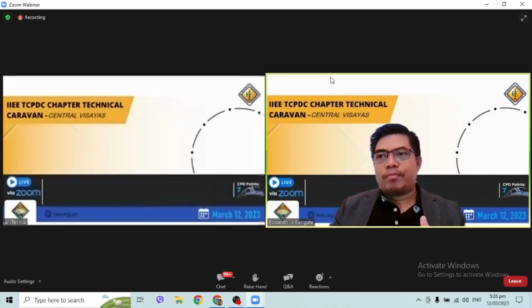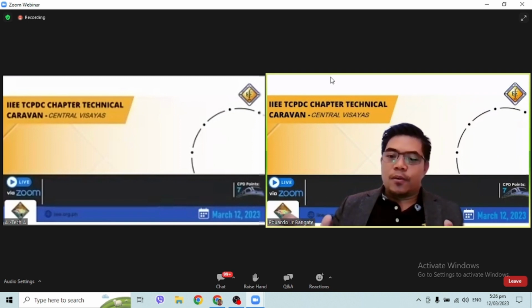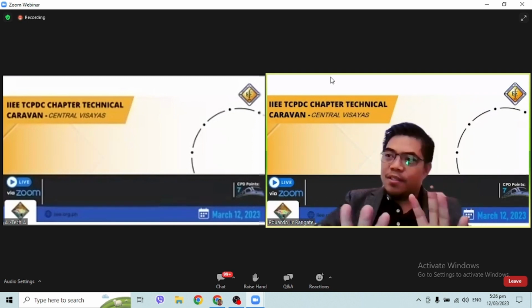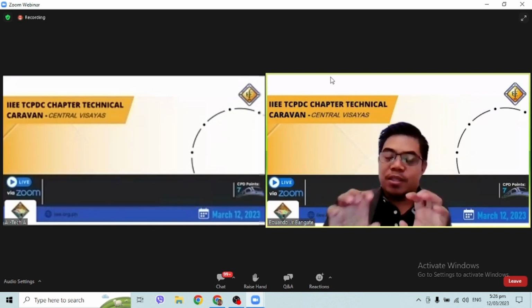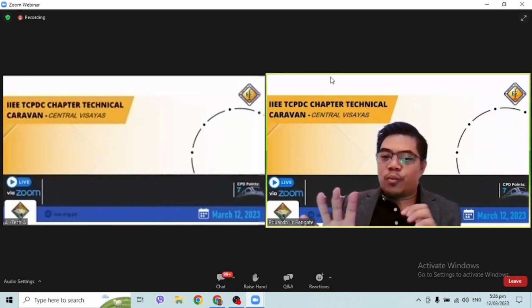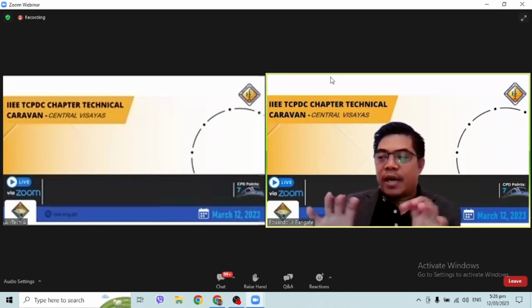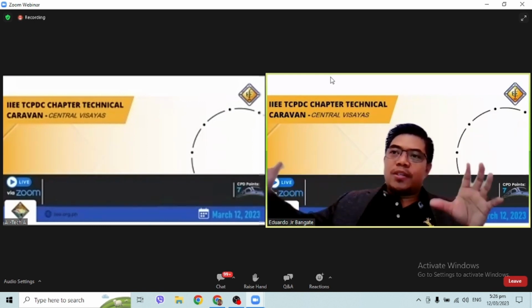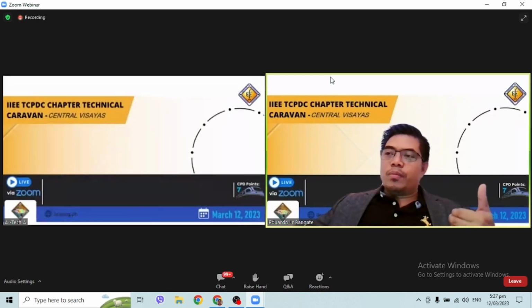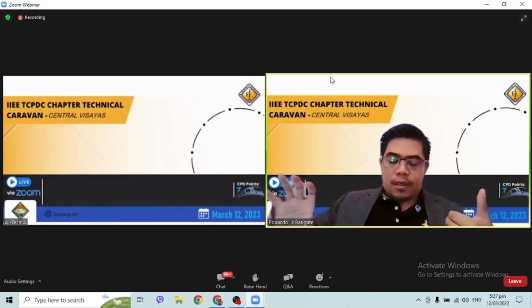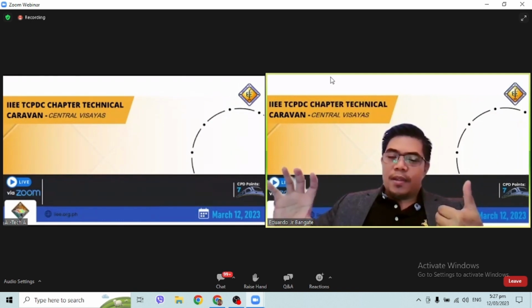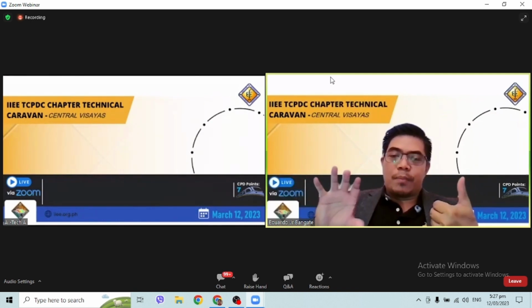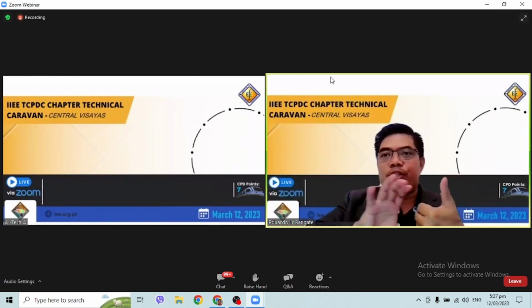It will synchronize, okay? And automatically, normally automatically, don't make it manual. It is very difficult, although you can do that by synchroscope, but it is very difficult to operate and synchronize in manual. Okay, so you have three generators, for example, then it will be running in what we call global running. And then the system will detect after you started your biggest load. Normally you start the biggest load.